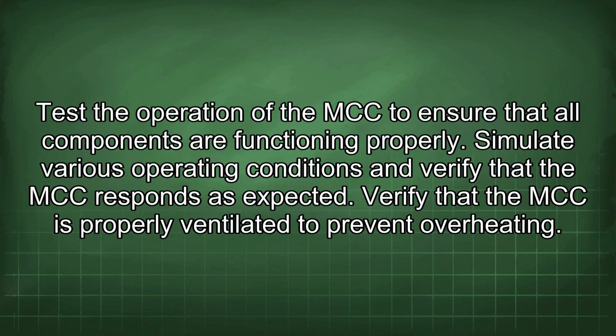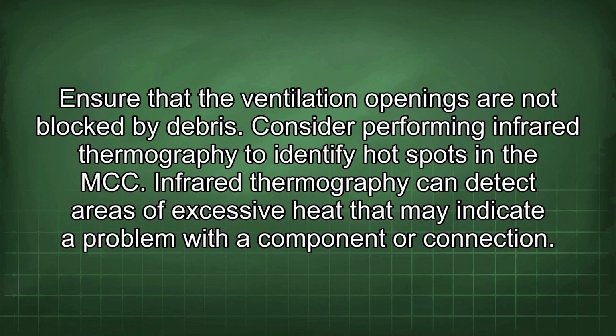Test the operation of the MCC to ensure that all components are functioning properly. Simulate various operating conditions and verify that the MCC responds as expected. Verify that the MCC is properly ventilated to prevent overheating. Ensure that the ventilation openings are not blocked by debris. Consider performing infrared thermography to identify hot spots in the MCC. Infrared thermography can detect areas of excessive heat that may indicate a problem with a component or connection.